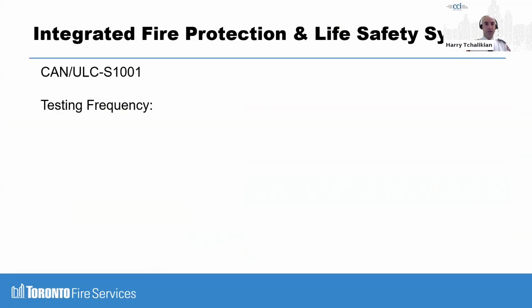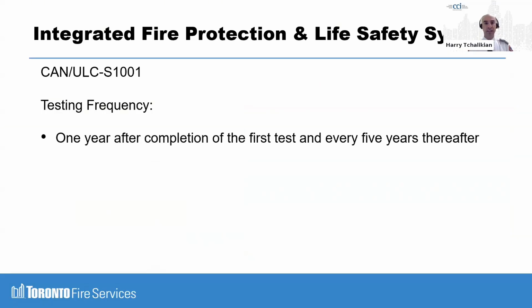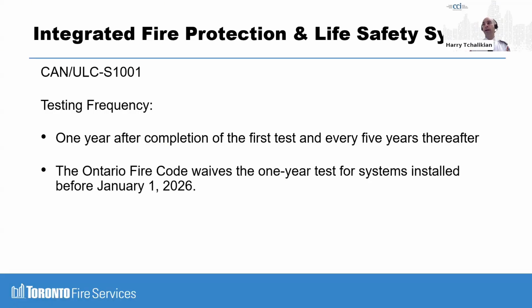Test frequency: 1 year after completion of the first test, which would have been what the building division did when they approved the building, and then 1 year after that, and then every 5 years thereafter. The Ontario Fire Code waives the 1 year test for systems installed before January 1st, 2026. So starting now, basically. But this comes into effect for systems that were installed as of January 2020, so anything built, whether the whole building or just a new system installed in an existing building, in 2020 and 2021 is now due for its 5 year test.